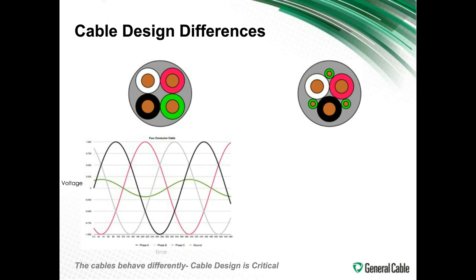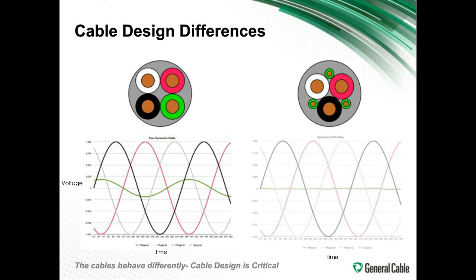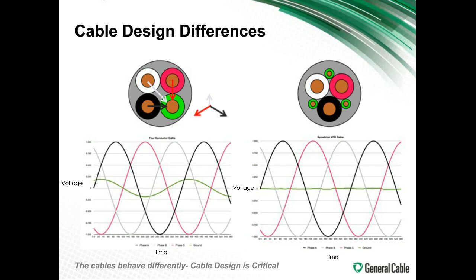Now if you look at the right, you have three grounds all put into the cable in a symmetrical fashion. Because these are evenly spaced, you will see that the green here shows the voltage created by the cable is minimal because they all cancel each other out. This happens because if you look on the left, at the arrow, the distance to the ground is different from each conductor. That's important. So that's where you see the differential. If you look at the distance to each ground from each conductor on the right-hand side, they're even, so they cancel each other out.